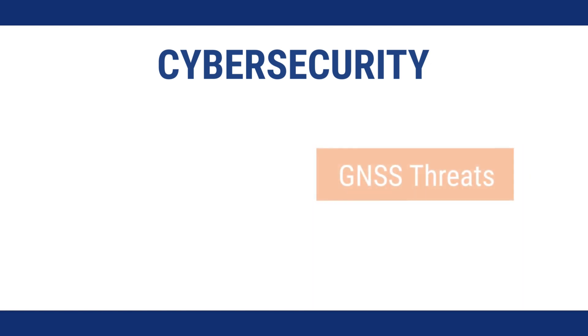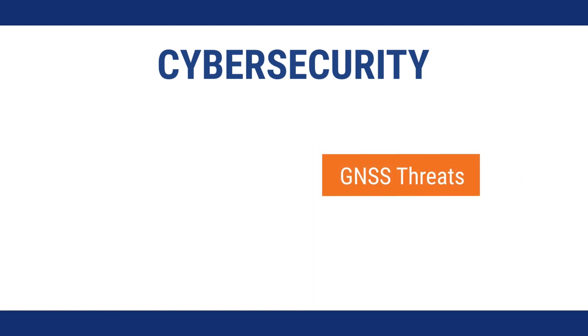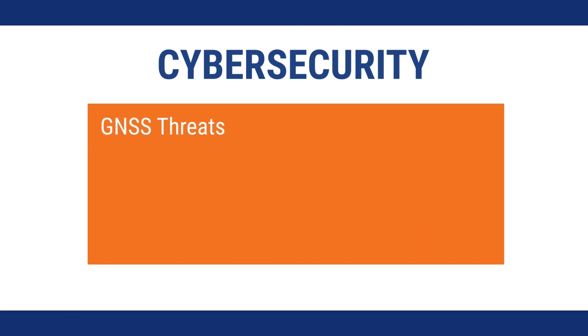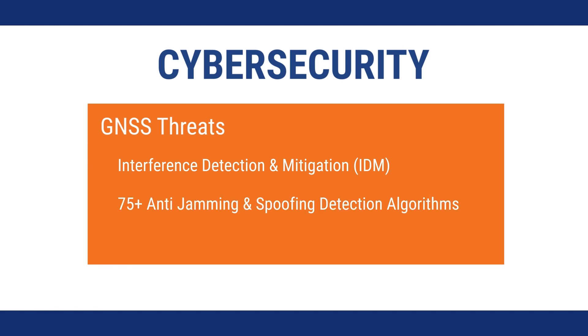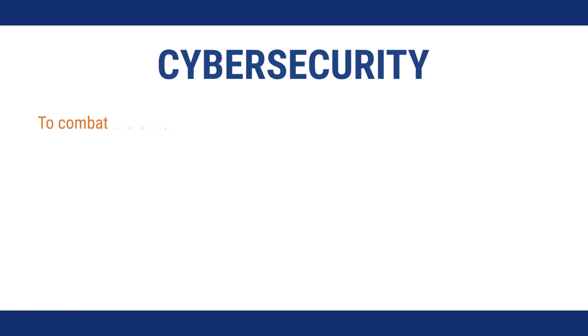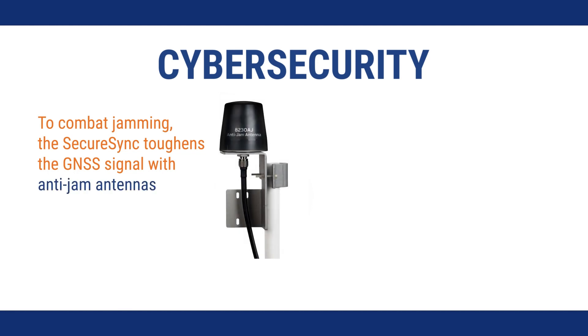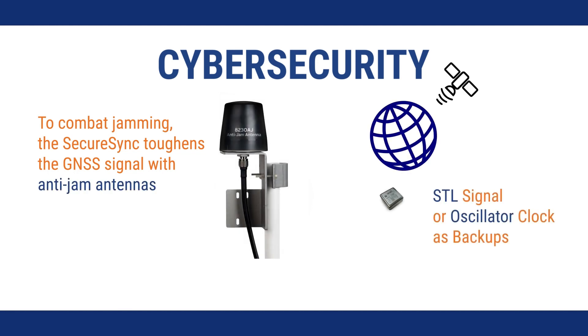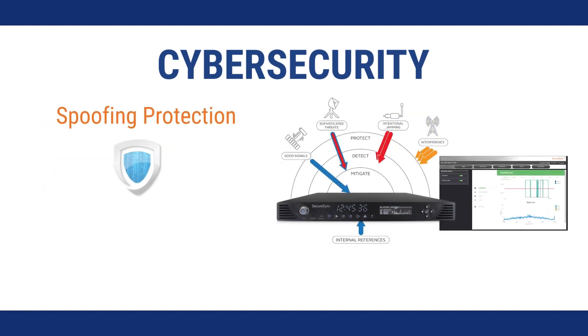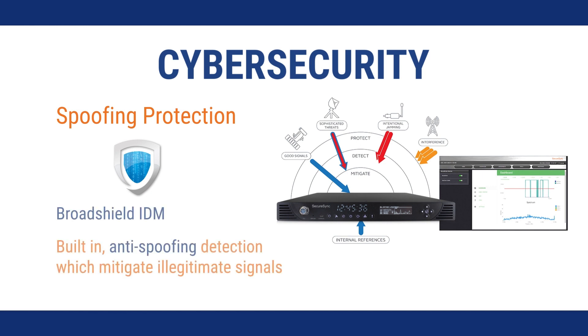SecureSync protects against GNSS security threats with a built-in interference detection mitigation suite, or IDM. IDM employs anti-jamming and spoofing algorithms to detect signal threats. To combat jamming, the SecureSync toughens the GNSS signal with anti-jam antennas, or by allowing you to choose an alternative timing source when GNSS is lost. To protect against spoofing, the SecureSync comes with built-in anti-spoofing software which can recognize and mitigate illegitimate signals.